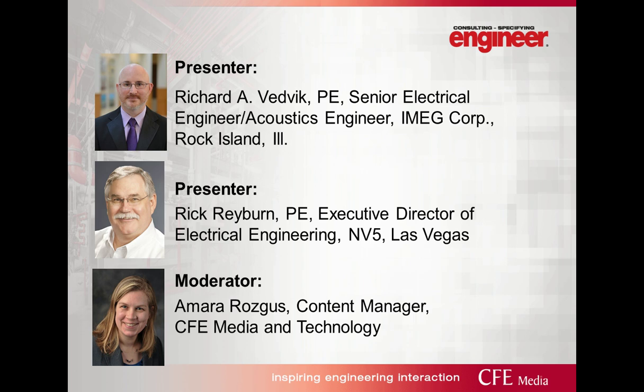You're always going to think about, do I have separately derived systems or not on the generator as well as the utility, and what's that pathway back for the neutral current? Because remember, our neutral is giving us a pathway back to our normal source. I've done generator installations that were a high impedance neutral, so they were a Y 480 volt generator, but instead of taking the neutral conductor to the paralleling gear, we would run that through a high impedance resistor or a neutral grounding resistor.